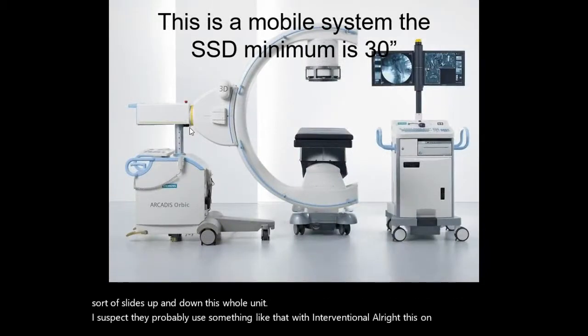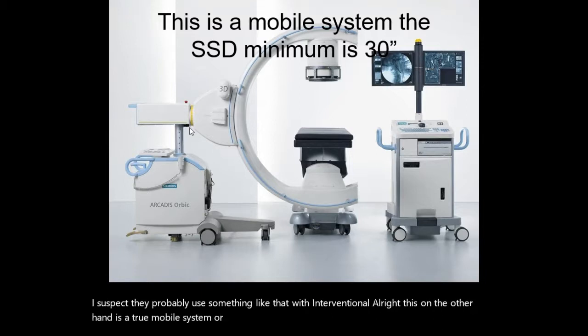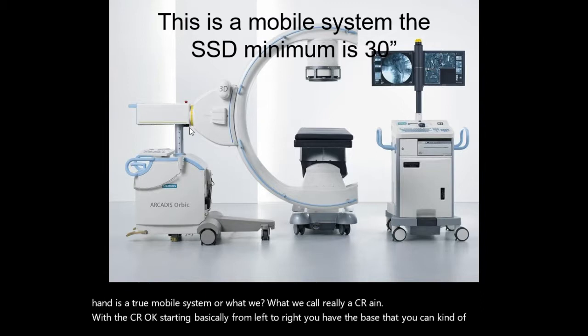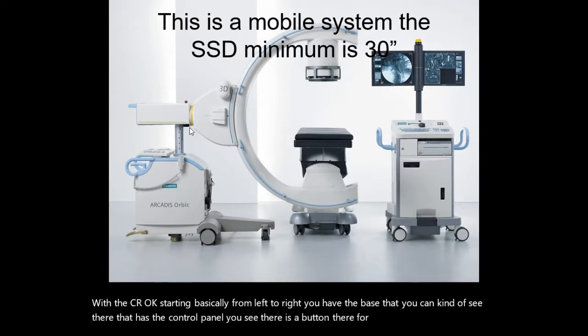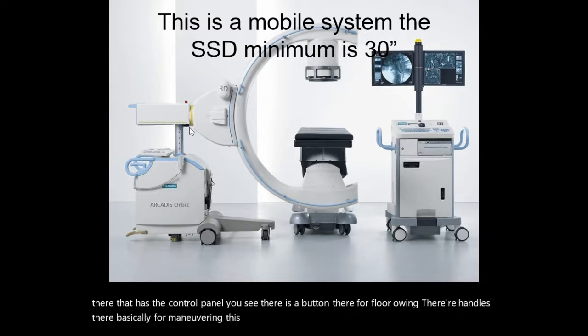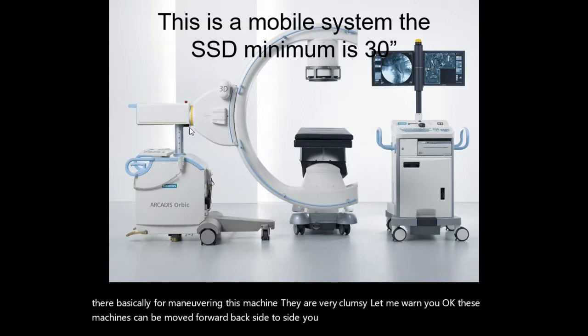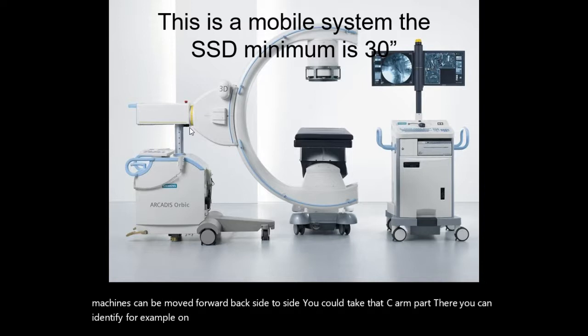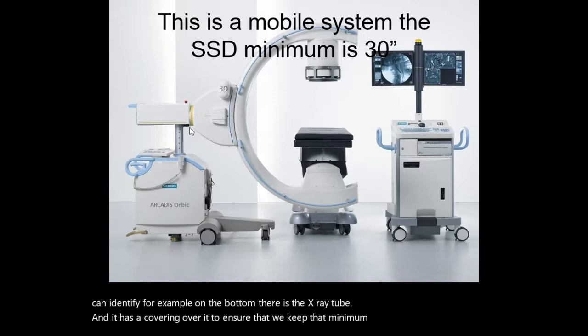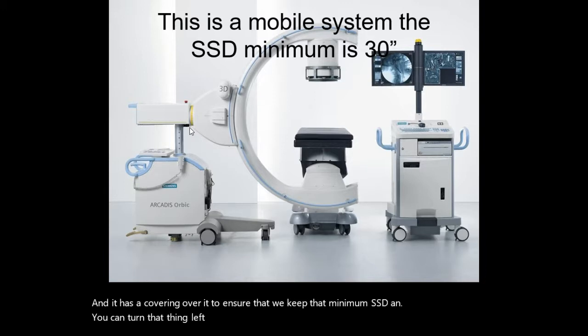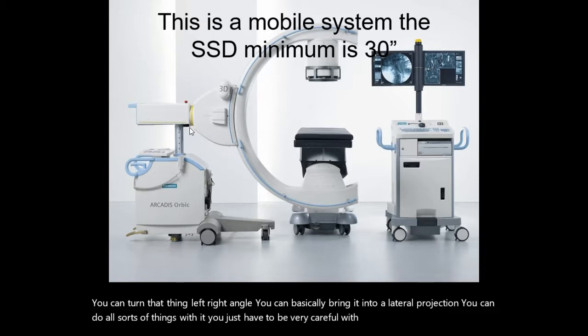All right, this, on the other hand, is a true mobile system, or what we call really a C-arm. With the C-arm, starting from left to right, you have the base that has the control panel. You see there is a button there for fluoroing. There are handles for maneuvering this machine. They are very clumsy, let me warn you. These machines can be moved forward, back, side to side. You can take that C-arm part there. You can identify, for example, on the bottom, the X-ray tube, and it has a covering over it to ensure that we keep that minimum SSD. And you can turn that thing left, right, angle it. You can bring it into a lateral projection. You can do all sorts of things with it. You just have to be very careful with it because it's big and it's clumsy.